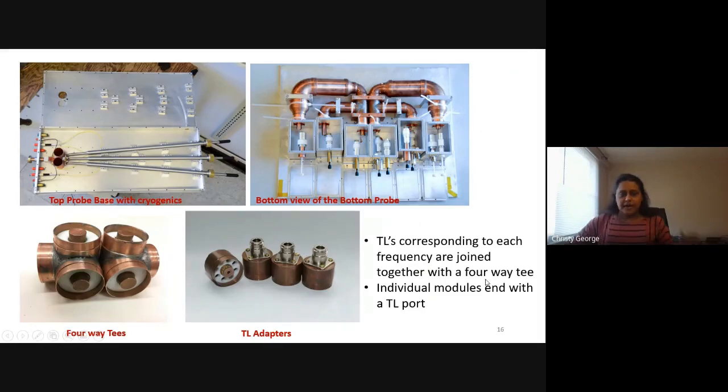Now, these are all the parts of the probe. These are the bearing, drive and VT points, where we use cold nitrogen gas to spin the sample, and the sensors, the temperature sensor and the spin sensor, all of these are connected right here.